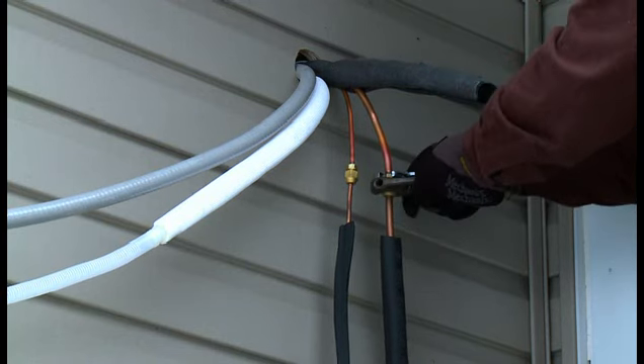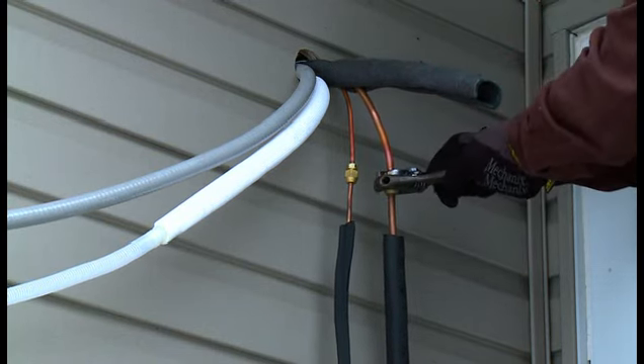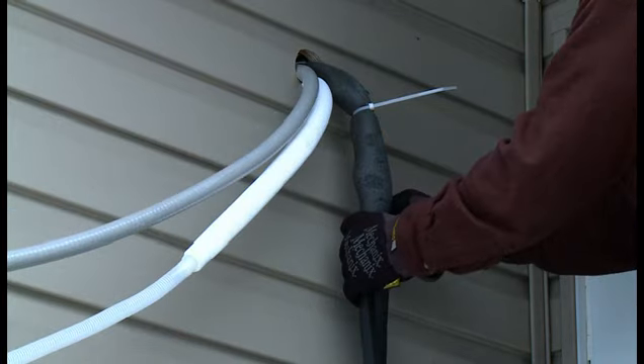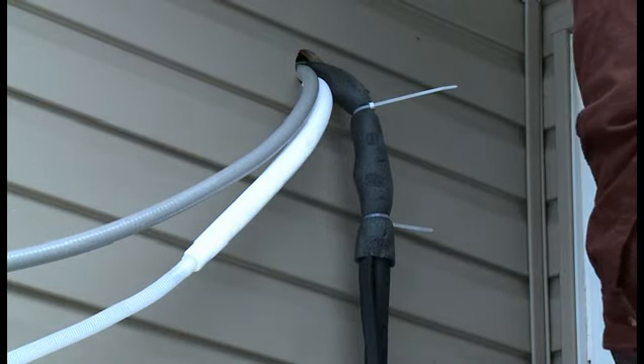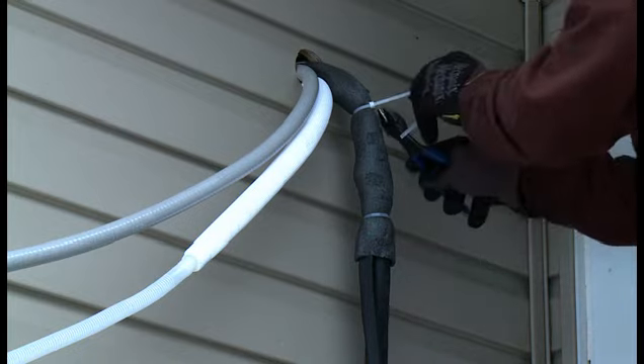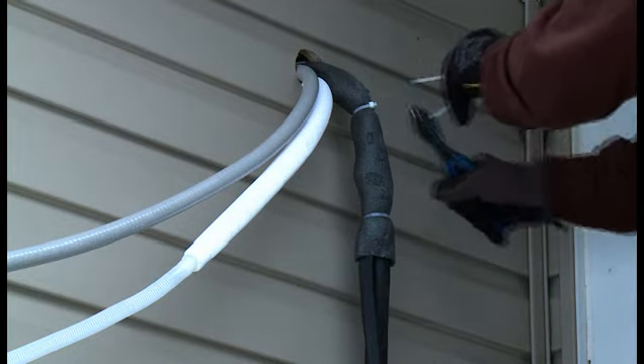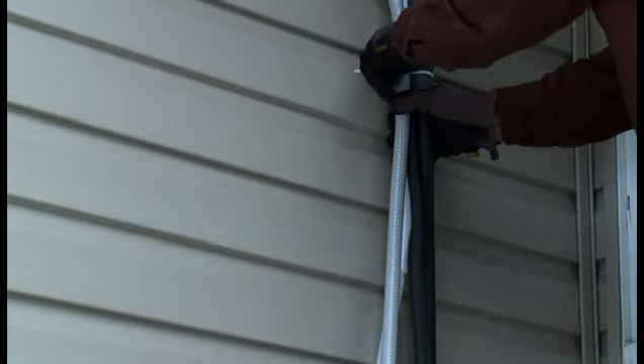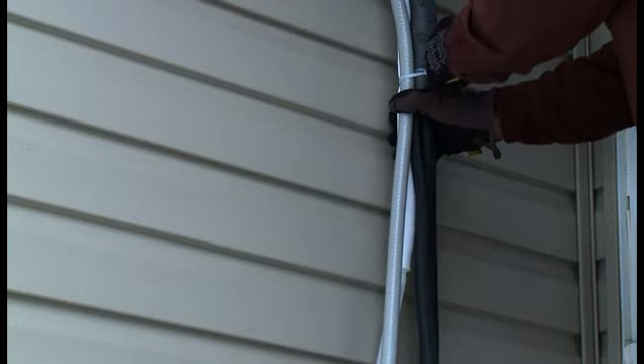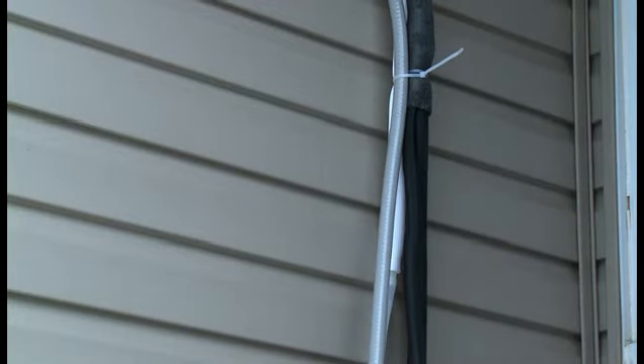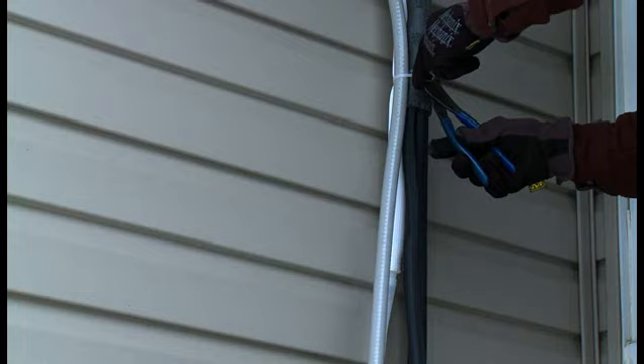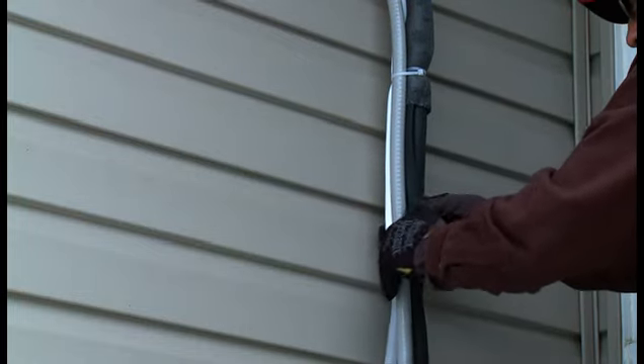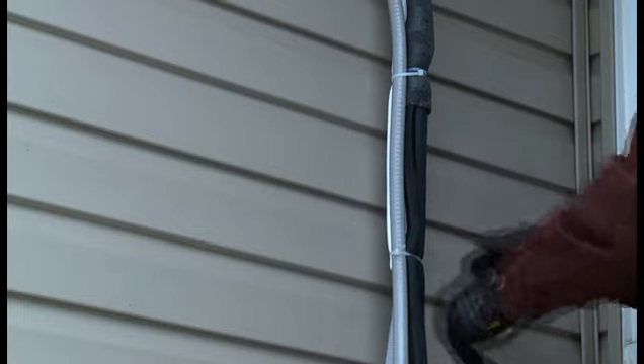Using open-ended or adjustable wrenches, tighten the flare nuts. Replace the insulation and secure with nylon cable ties. Trim away the excessive nylon. Next, again using the nylon cable ties, bundle together the drain hose, line set, and control wire conduit. Remove the excess nylon. Continue bundling the drain hose, line set, and conduit to make it secure.